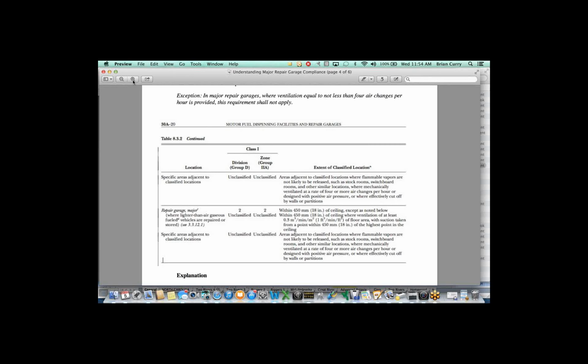And that's excessive. If you run an exhaust system at 5 air exchanges per hour, you can definitely feel it. As a matter of fact, if you install that many fans with the rated CFMs and did not include a fresh air intake, you could not even open the man doors leading to the outside. It would just suck the doors right to the building. So consider it emergency shop ventilation.